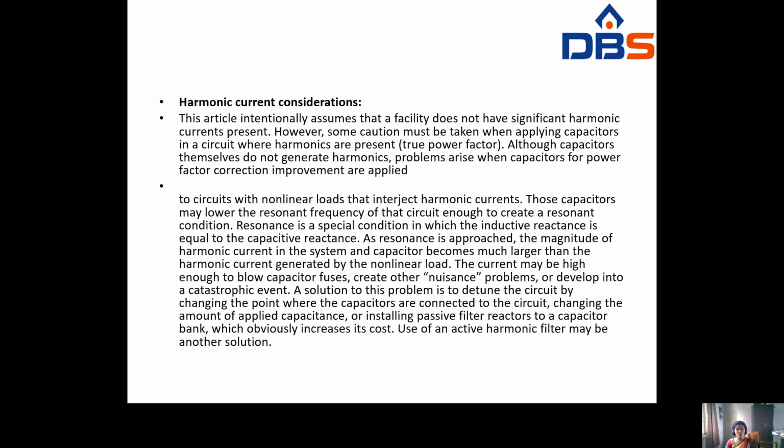As resonance is approached, the magnitude of the harmonic current in the system and capacitors becomes much larger than the harmonic current generated by the non-linear load. The current may be high enough to blow capacitor fuses and create other nuisance problems. The solution is to detune by changing the point where capacitors are connected.